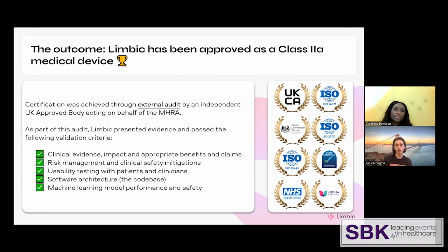We also had to do some work on additional risk management. So many of you will be familiar with the DCB standard of clinical risk management in the NHS, but above and beyond this, there's a medical device risk management standard, 14971, that is similar to the DCB in areas, but also has some additional factors and additional things you need to consider and do as part of your risk mitigation activity. So we had to do this one piece around building the framework and the blueprint and the machinery in this aspect.